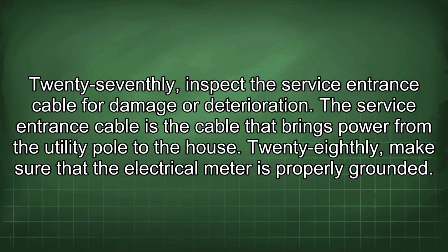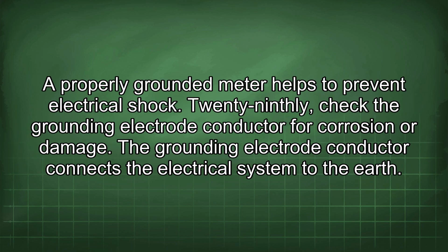27thly, inspect the service entrance cable for damage or deterioration. The service entrance cable is the cable that brings power from the utility pole to the house. 28thly, make sure that the electrical meter is properly grounded. A properly grounded meter helps to prevent electrical shock. 29thly, check the grounding electrode conductor for corrosion or damage. The grounding electrode conductor connects the electrical system to the earth.